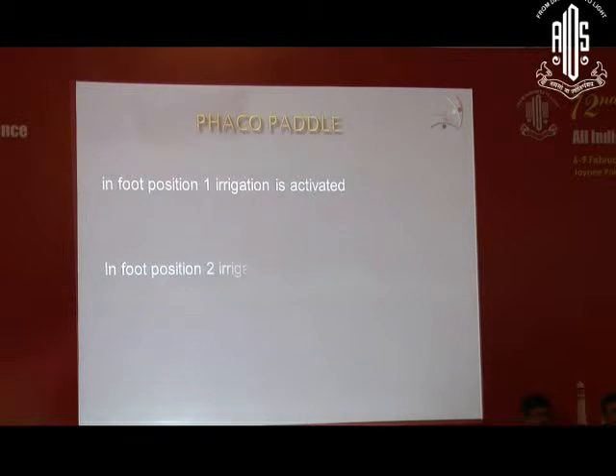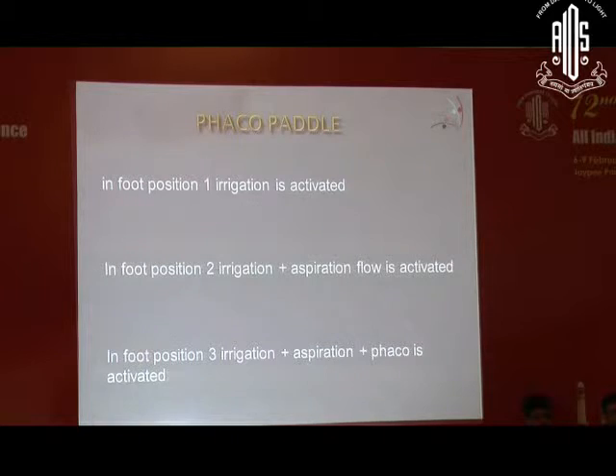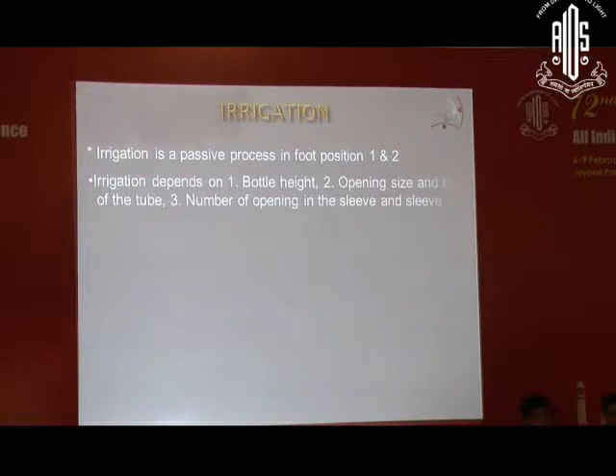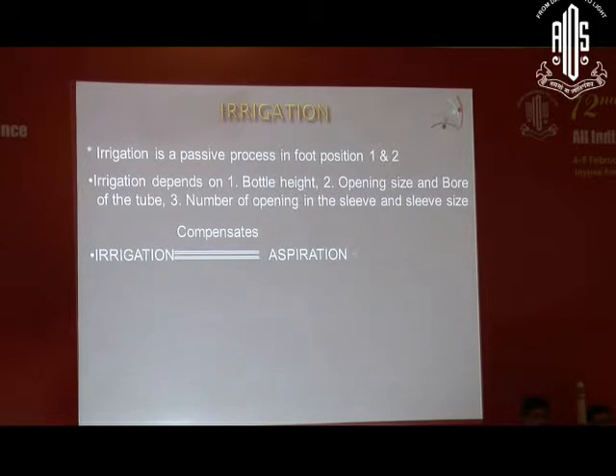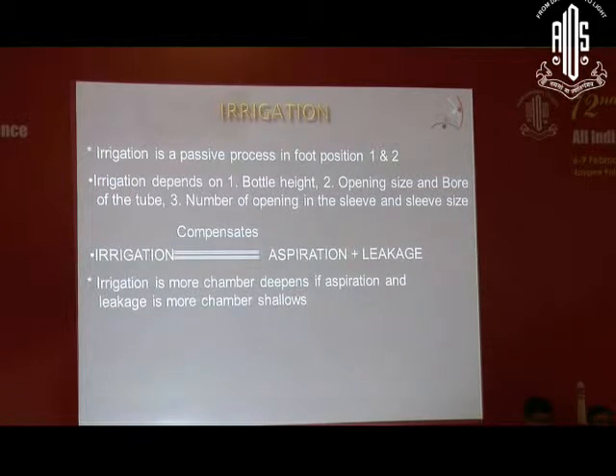In foot position 1, irrigation is activated. In foot position 2, irrigation and aspiration flow is activated. And in foot position 3, all three, that is the phaco is activated, more important. Irrigation is a passive process in foot position 1, 2 and 3. Irrigation depends upon the bottle height, the bore size of the tube, the number of openings in the sleeve, the size of the sleeve. But this is almost constant for a particular machine or a particular setup. And irrigation is compensated by aspiration plus a little bit of fluid which leaks from the sides. Now if irrigation is more, the chamber deepens, and if the aspiration and leakage is more, the chamber will shallow.